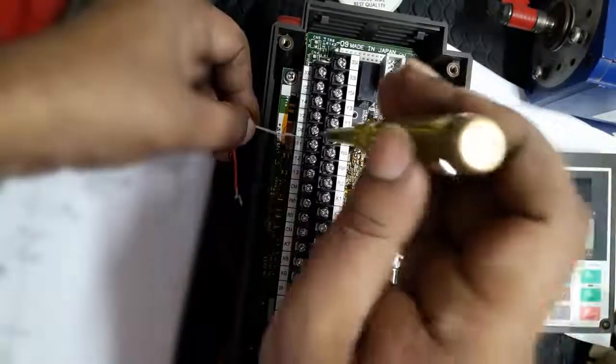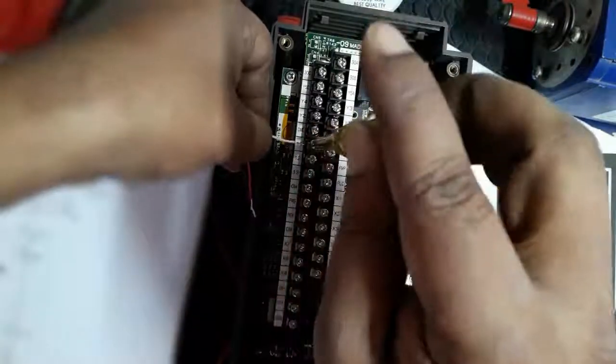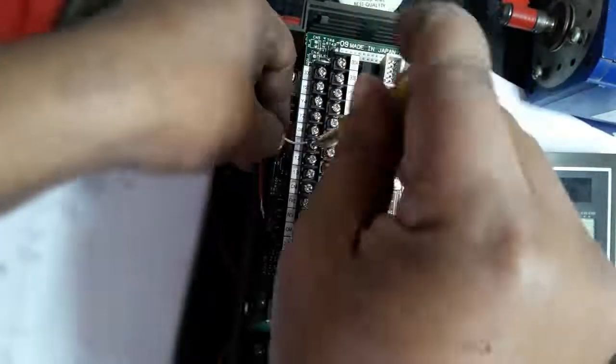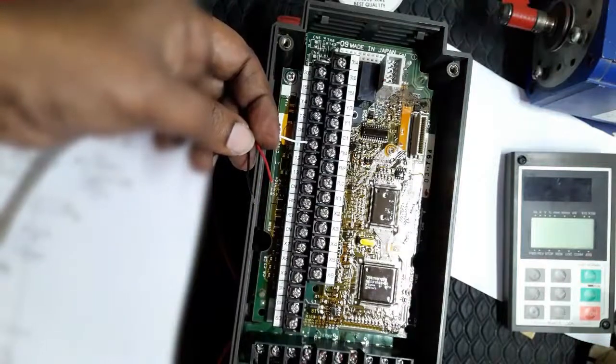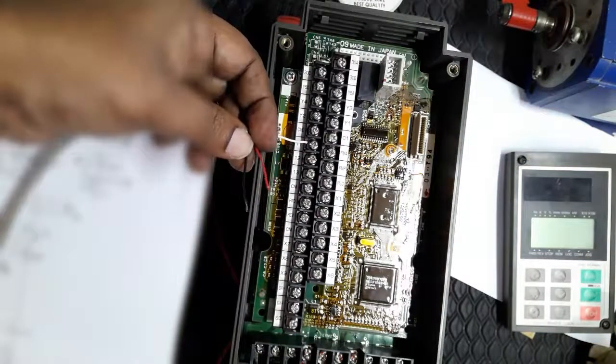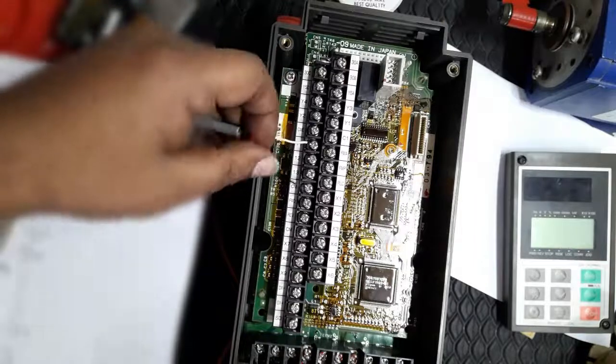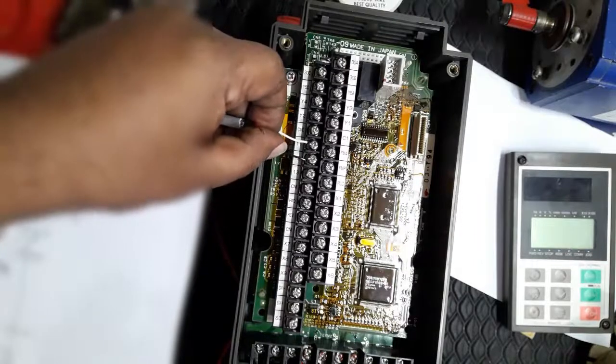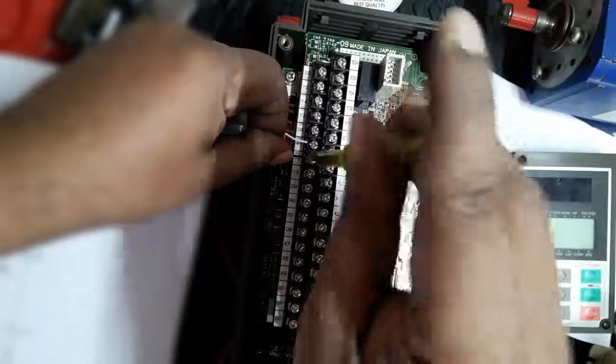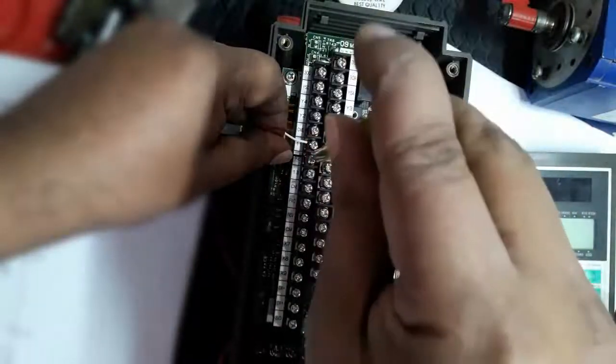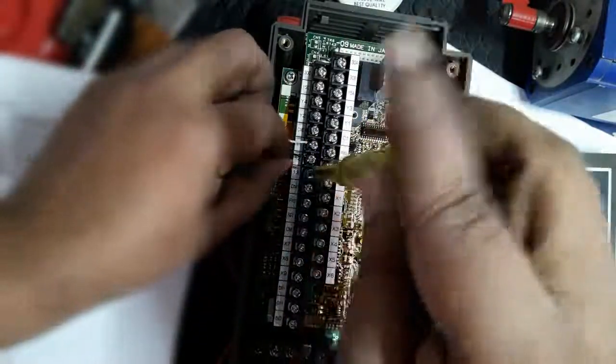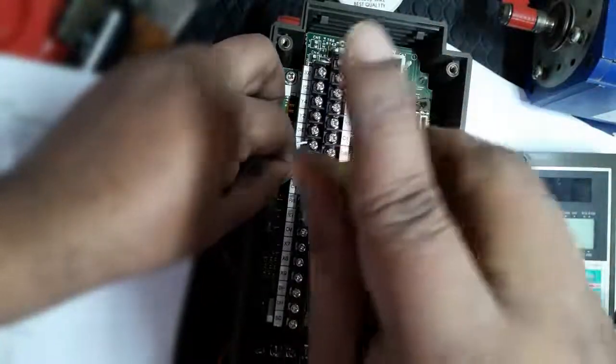First, we're setting a potentiometer in terminals 11, 12, and 13, which are dedicated for potentiometer. So we connected here a variable potentiometer for external run command or external frequency operation.